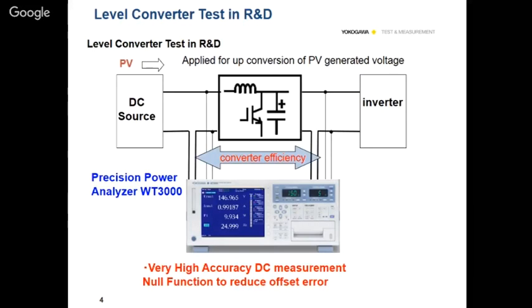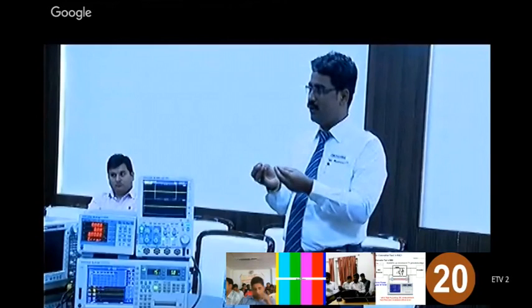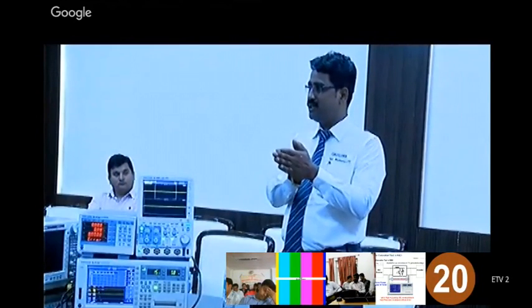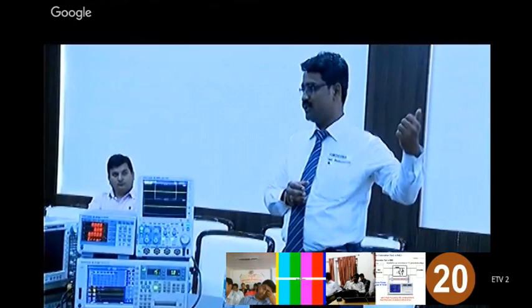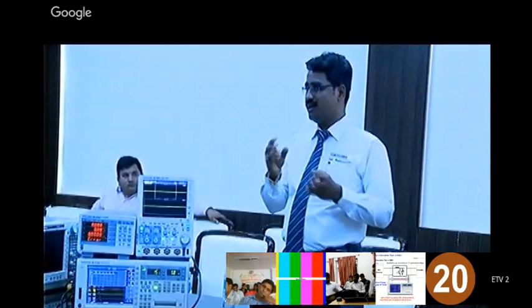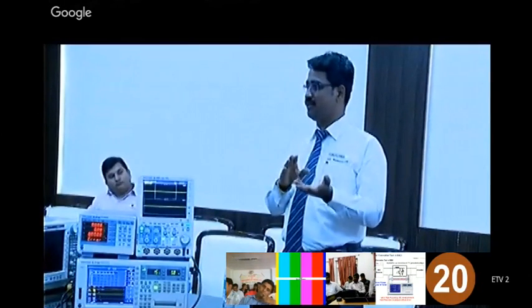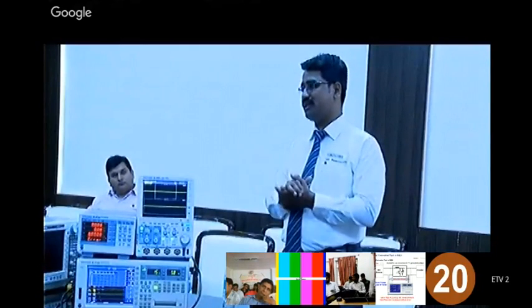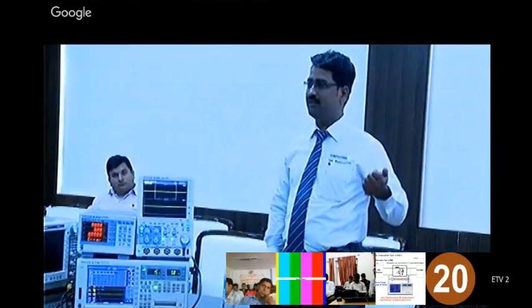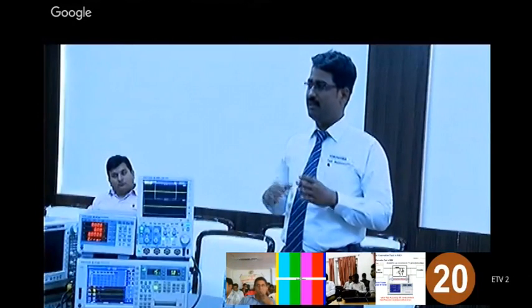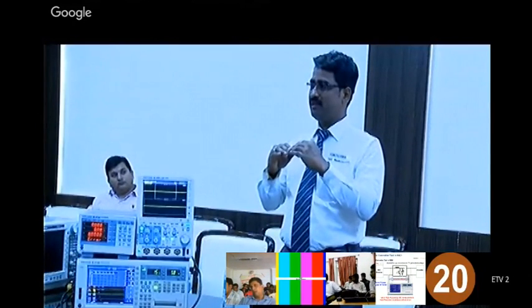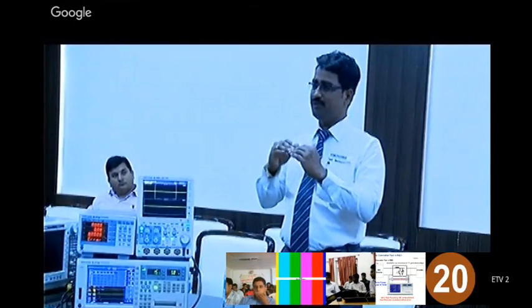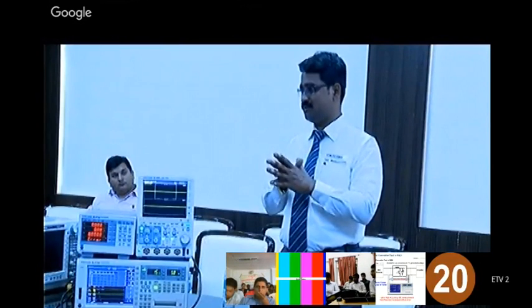If you don't enable the null function, that additional offset gets added to either the input or output side, giving either positive or negative side efficiency errors—it may affect either side. But when you enable the null function, this can be avoided, establishing a zero point from which the efficiency is calculated.